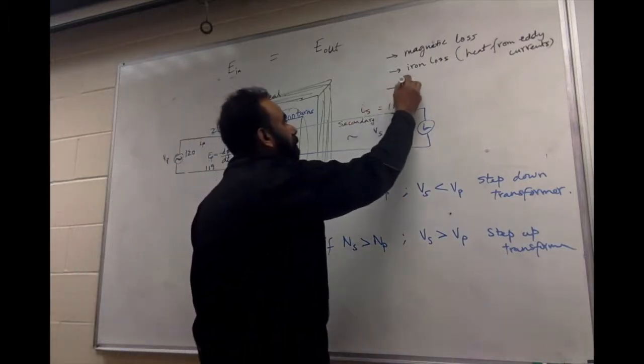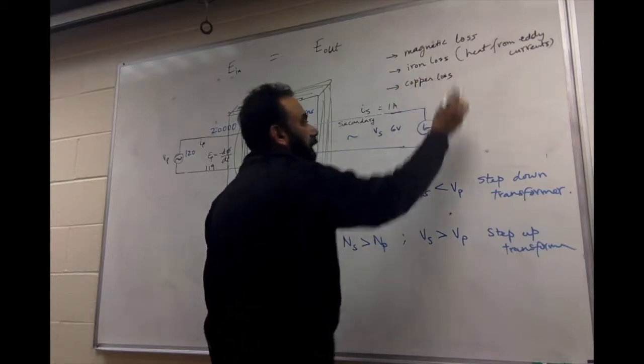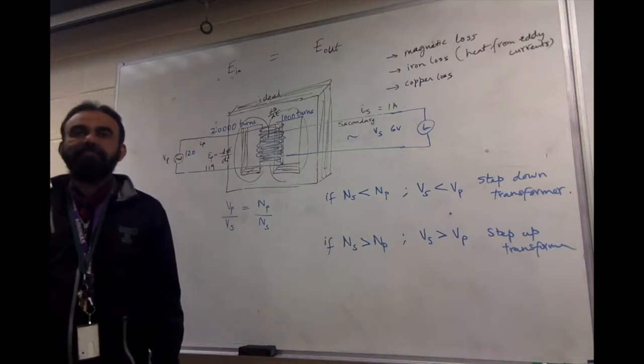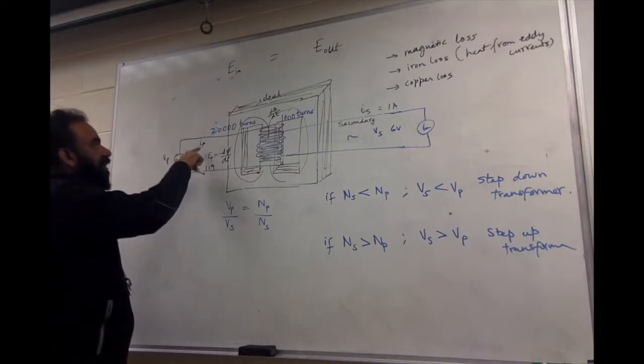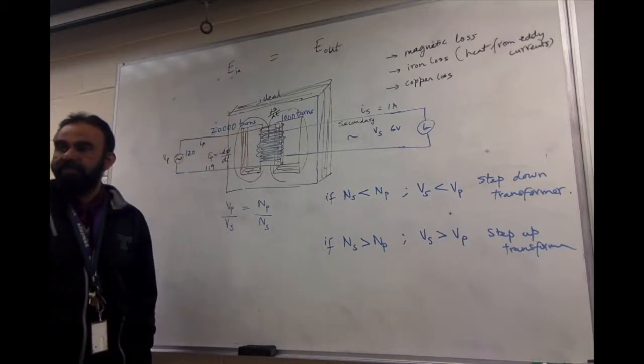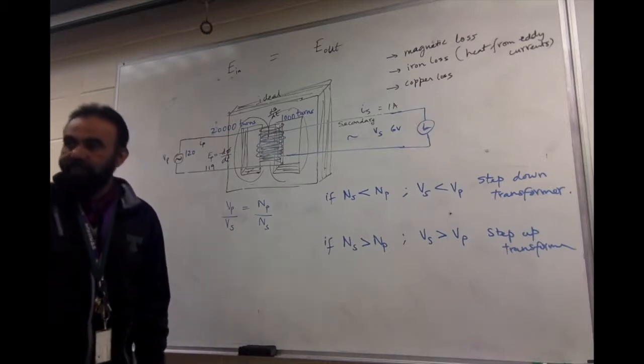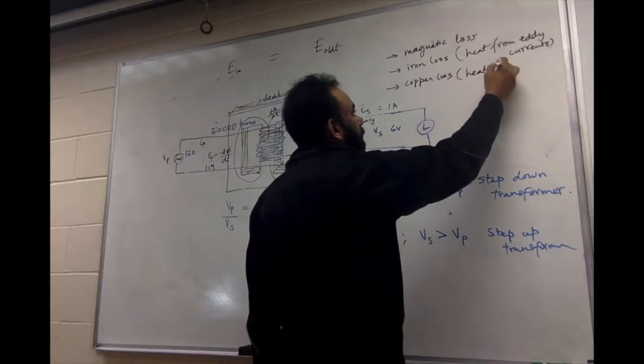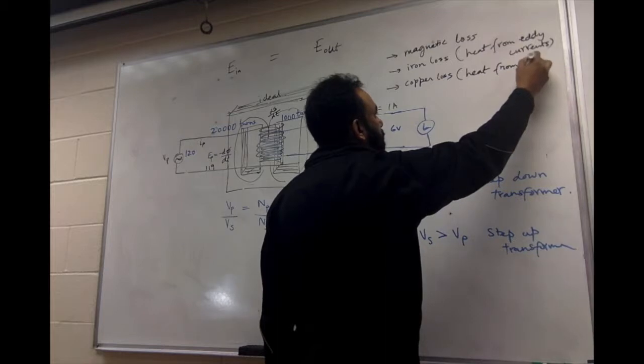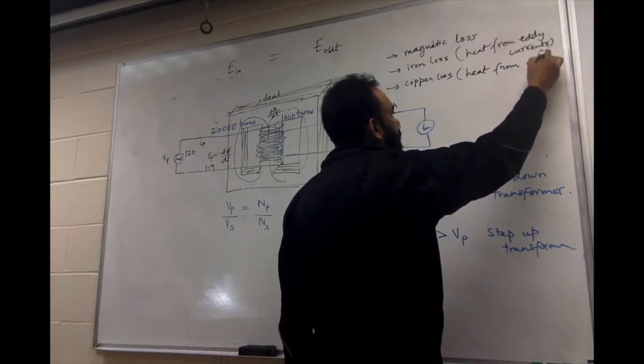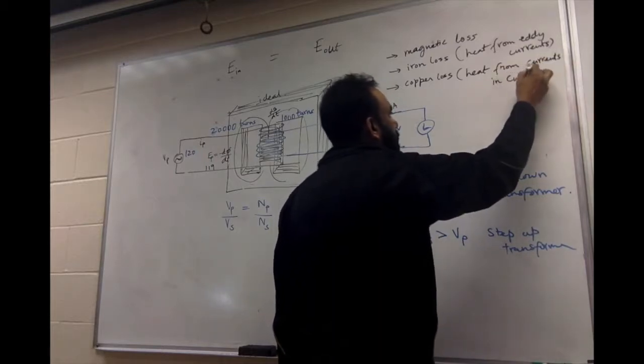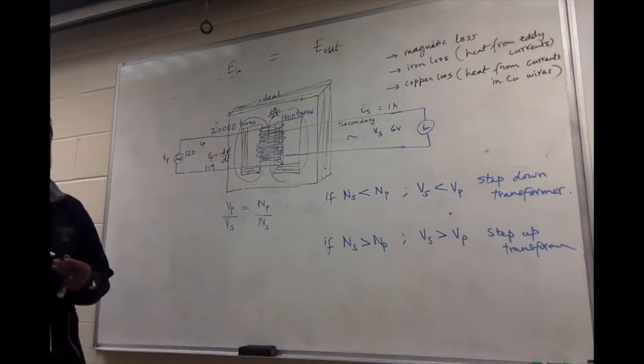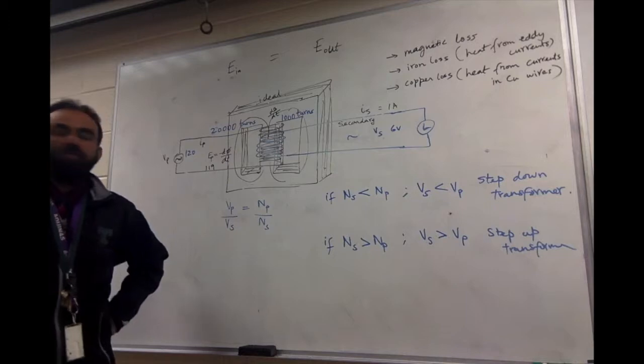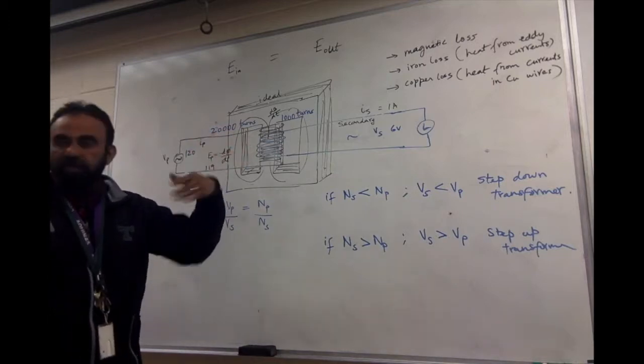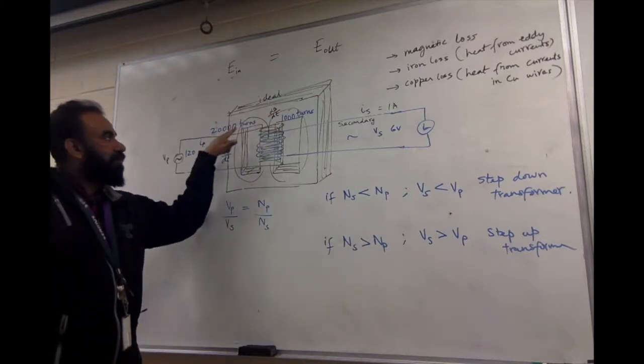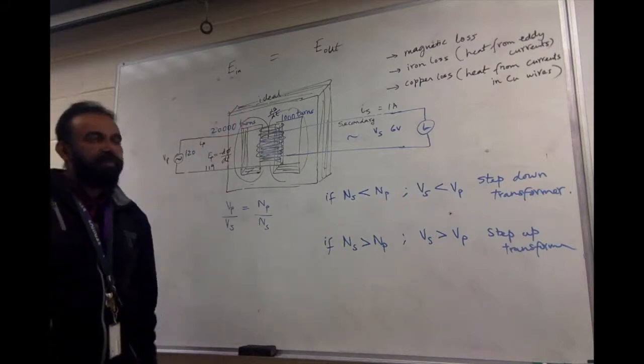Then the other kind of loss is the copper loss. Again, this is not about losing copper, what is lost? Heat in the copper wires. Because you have a current flowing through copper wires, and copper wires do have some resistance, so there's an I-squared-R heating effect that takes place there. So copper loss is the heat from the currents in the copper wires, iron loss is the heat from the eddy currents, and there are also magnetic losses. All these are responsible for a transformer not being ideal.